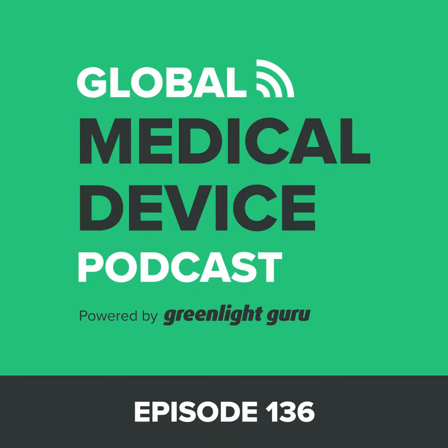The device needs to come in contact with body tissue. That's what FDA says in the description. It needs to come in contact with body tissue, but that does not mean it needs to come in contact with the body. So to me, one of the applicable technologies that might be attractive to people who want to try this is in vitro diagnostics. Yeah, because in IVDs, as you know, John, you're taking tissue, a blood sample or something like that from the patient, and you're putting it in contact with your device. So the regulation says the device must come in contact with body tissue. It does not say it must come in contact with the body or that it must be invasive.